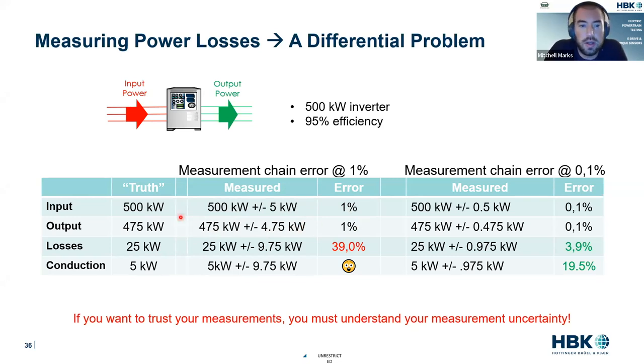But let's look at the losses. Well, we have 25 kilowatts of loss. We have to take 5 kilowatts on the input plus 4.75 kilowatts on the output to get that differential. So if we say we have 25 kilowatts of loss, well, that's 25 kilowatts plus or minus an uncertainty of 9.75 kilowatts. That's a 39% error. Do we really understand if the decisions we're making matter?